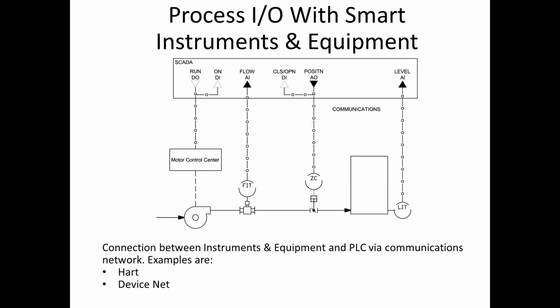That is sending, instead of a 4 to 20 milliamp signal, a signal that says I'm at this flow rate. So you don't need to convert that. It tells the PLC exactly what the flow is. And for example, the PLC can send information to the valve that says open up an additional 5%. And then the level indicating transmitter doesn't say it's at 100%. It tells you it's at 4 feet, for example.